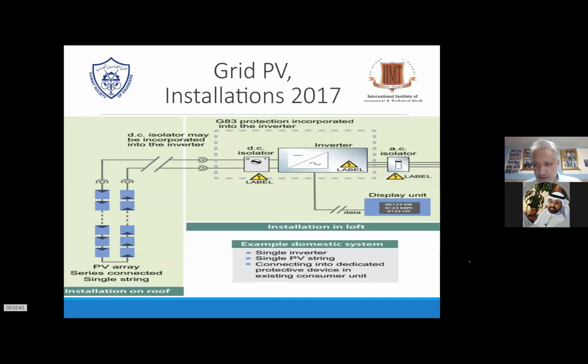So the inverter on these specific systems is just synchronizing more or less. So he doesn't do the MPPT. He has got a fixed MPPT, while the other inverters, like SMA, Fronius, many different suppliers, of course go with the AC current. So for example, if you have a single phase or a three-phase unit, and you have a really high voltage at the site, like we saw just before, the energy of the MPPT has to be higher. So the voltage needs to be upgraded at the inverter side.